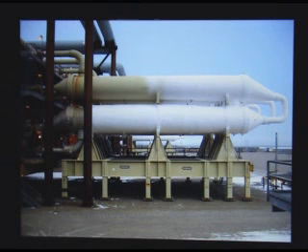However, they learned later on that ice builds up in the wintertime to a very thick layer, and when the weather changes, this ice comes down in big sheets and became dangerous. So I think in the future they might want to insulate this. Click again.